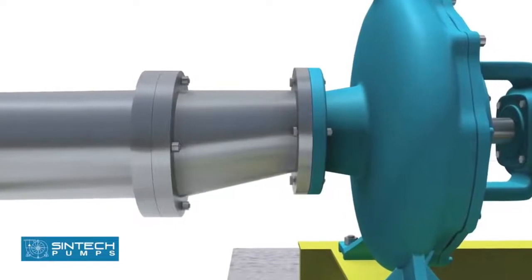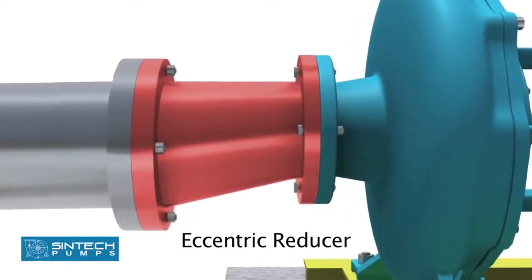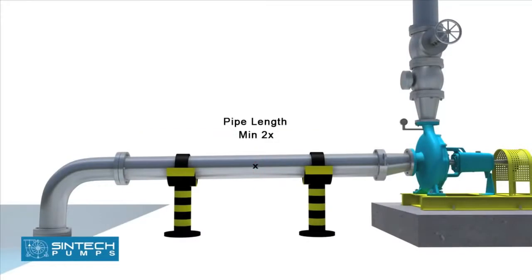The reducer joining the straight length of the pipe in the pump line should be an eccentric reducer with the inclined side of the reducer as the bottom side. The straight length of the pipe after the eccentric reducer should be 2 times the pipe diameter.